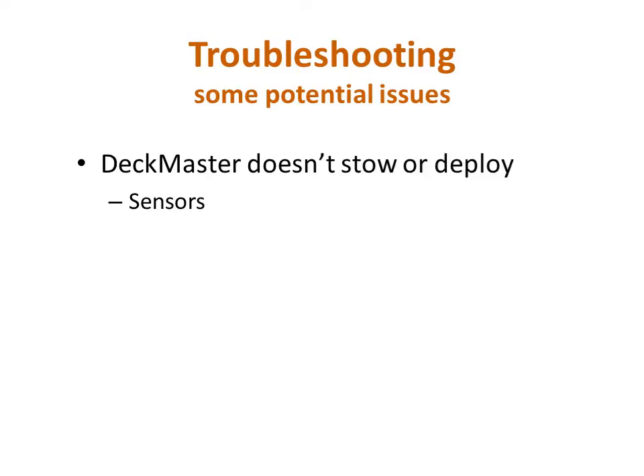Pin 28 on TB3 is responsible for supplying voltage to both sensors, and pin 26 on TB3 will register voltage when the rotation sensor is over the magnet completing the circuit. Please note though that since there is a resistor in the wiring harness, you should only get around 7.5 volts on pin 26 for a 12-volt system. After the monitor finds the rotation magnet, the nozzle then goes over backwards to its hard stop before the middle arm begins to move. To deploy, an almost identical process takes place.